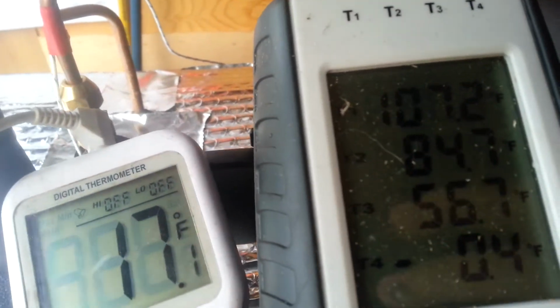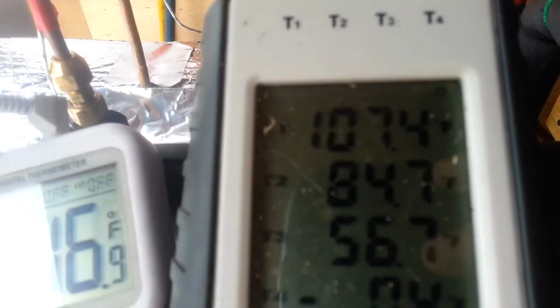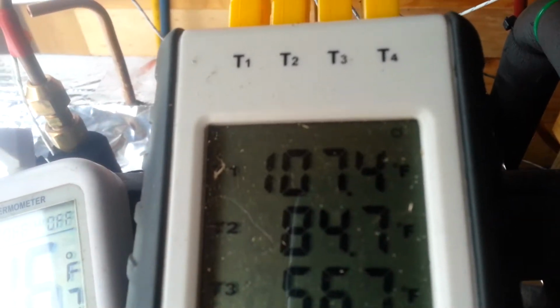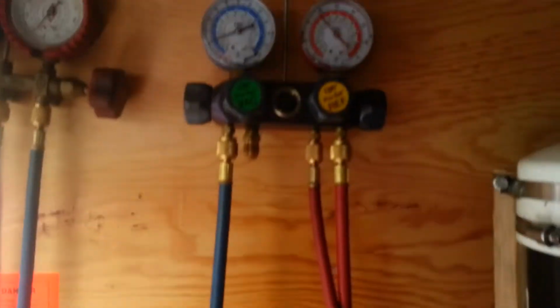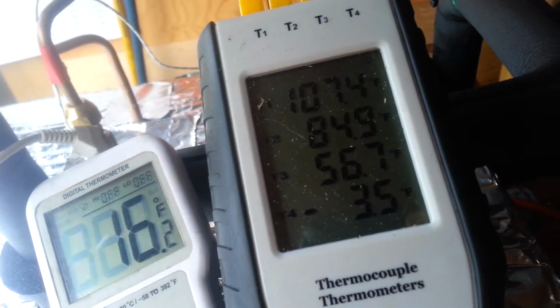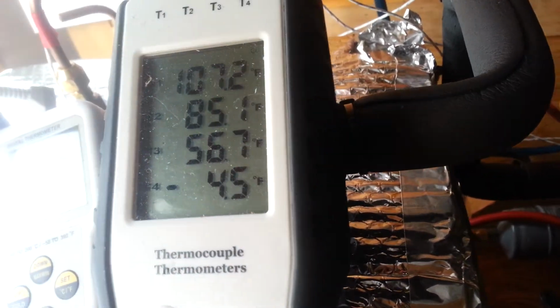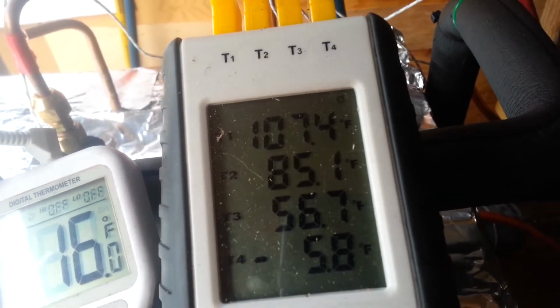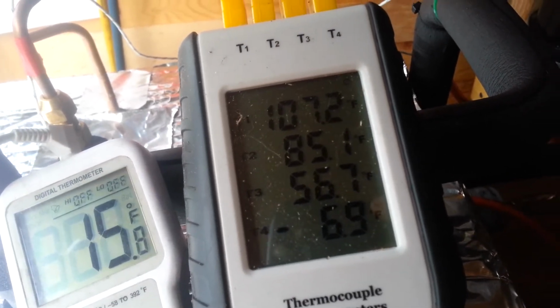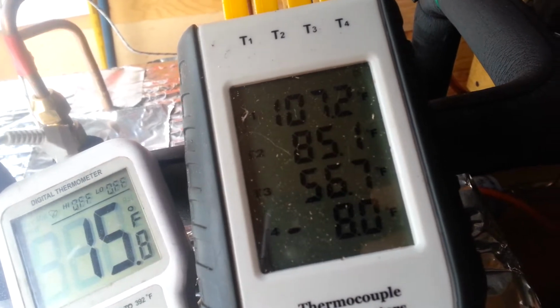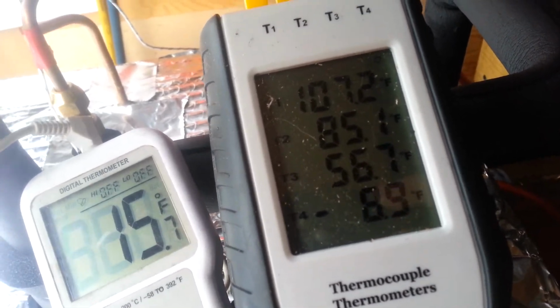And through various conditions all day long, I've seen temperatures as high as 138 degrees, actually 140 at one point on the high side, and it very, very closely corresponds to the pressure associated with that temperature. So it's pretty neat to see that close correlation. Is that an accurate number? Well, I'm sure it's not, but to see it track so well, all is within 1 to, I'd say, 4 degrees above what the corresponding condenser pressure or condenser temperature is at that pressure.